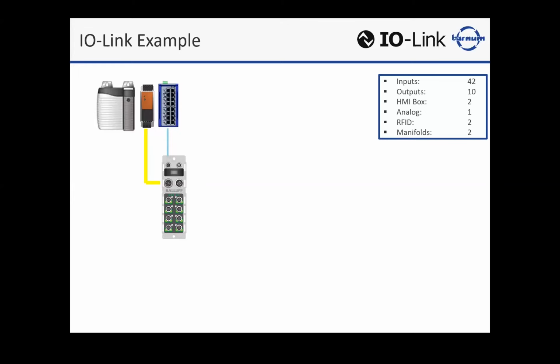So with this, you talked about having several devices. We're probably going to exceed the 8 on here. So let's add another IO-Link master. Yeah, and you'll see how that plays out. So now we have our 2 IO-Link masters consuming 2 IP addresses. Now we can start connecting these IO-Link devices, which are transparent to the PLC, and the PLC will see it as your upper level network.